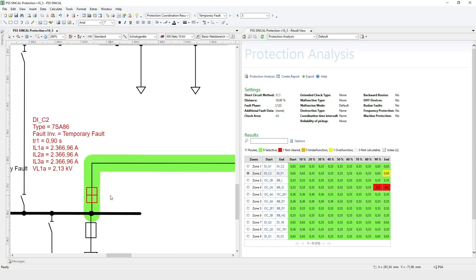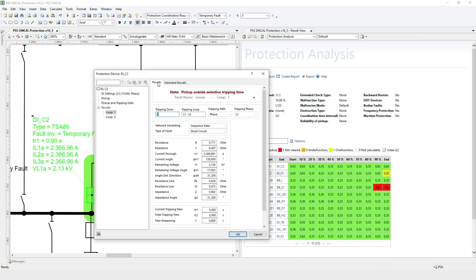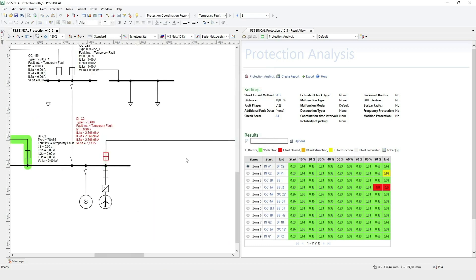Now let's look at the main protection for the highlighted protection area. The tripping time of device DI_C2 is 0.9 seconds, and for main protection this is quite high. If we check the results, we see zone 3 tripped. But usually the first and second zone are responsible for the main protection area, so we'd assume there is something wrong with the zone settings. We can use the protection route calculation to double-check.